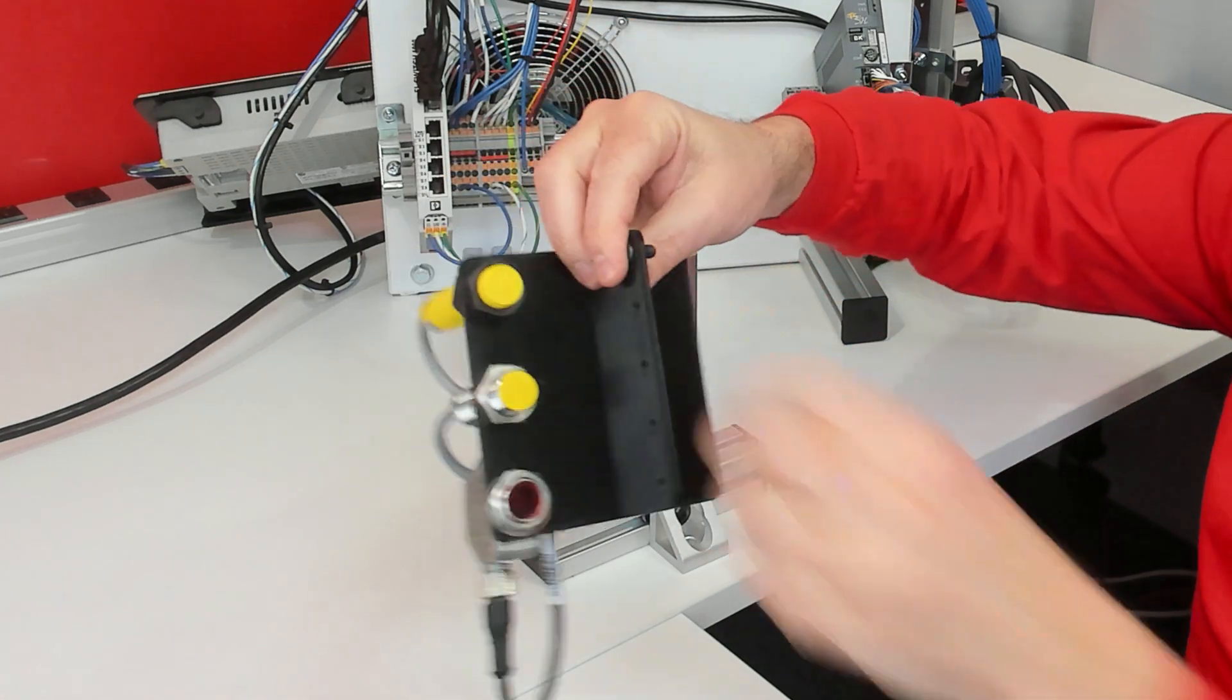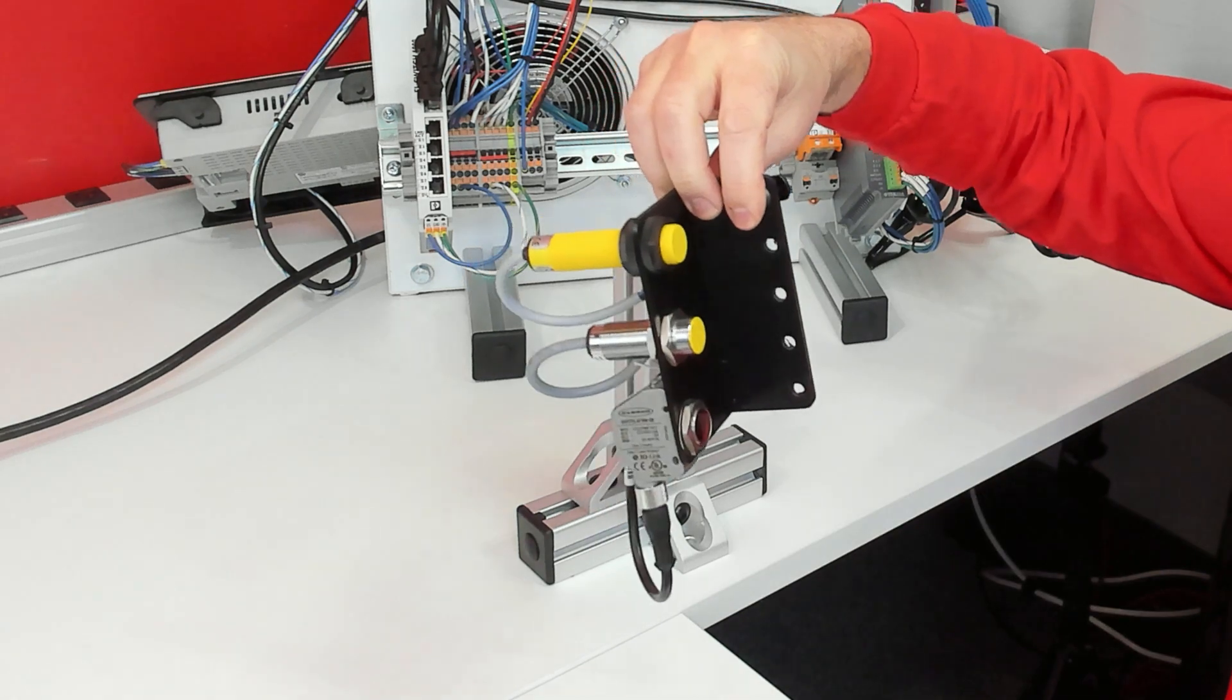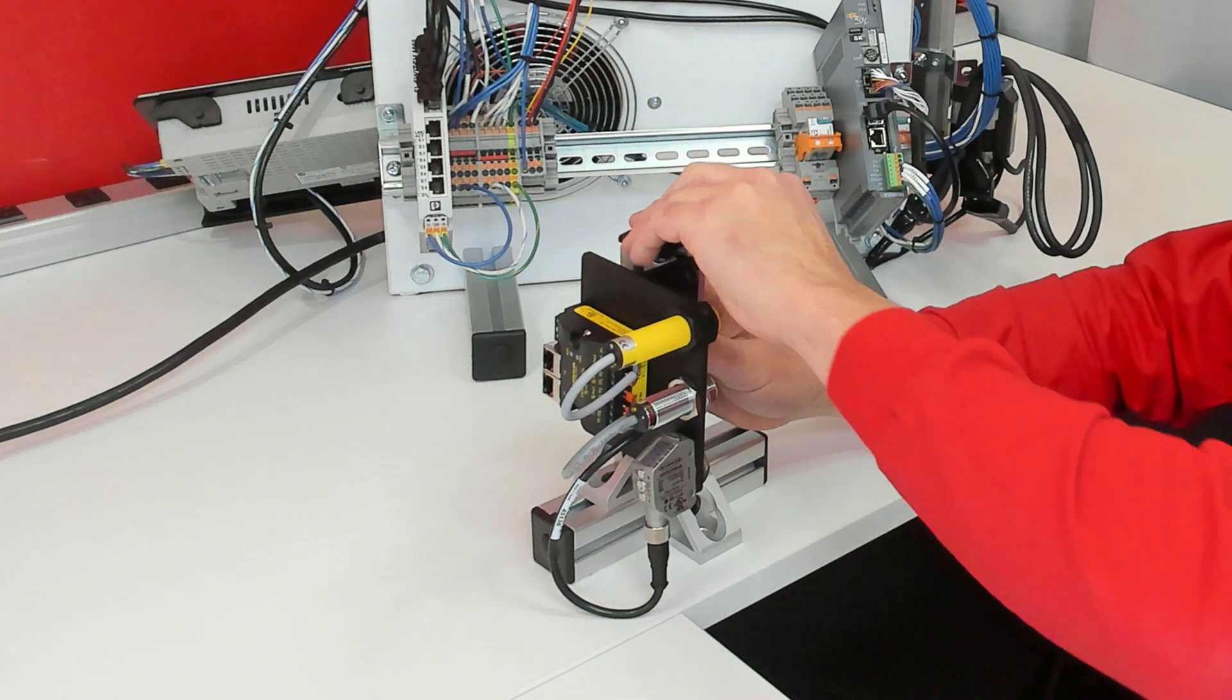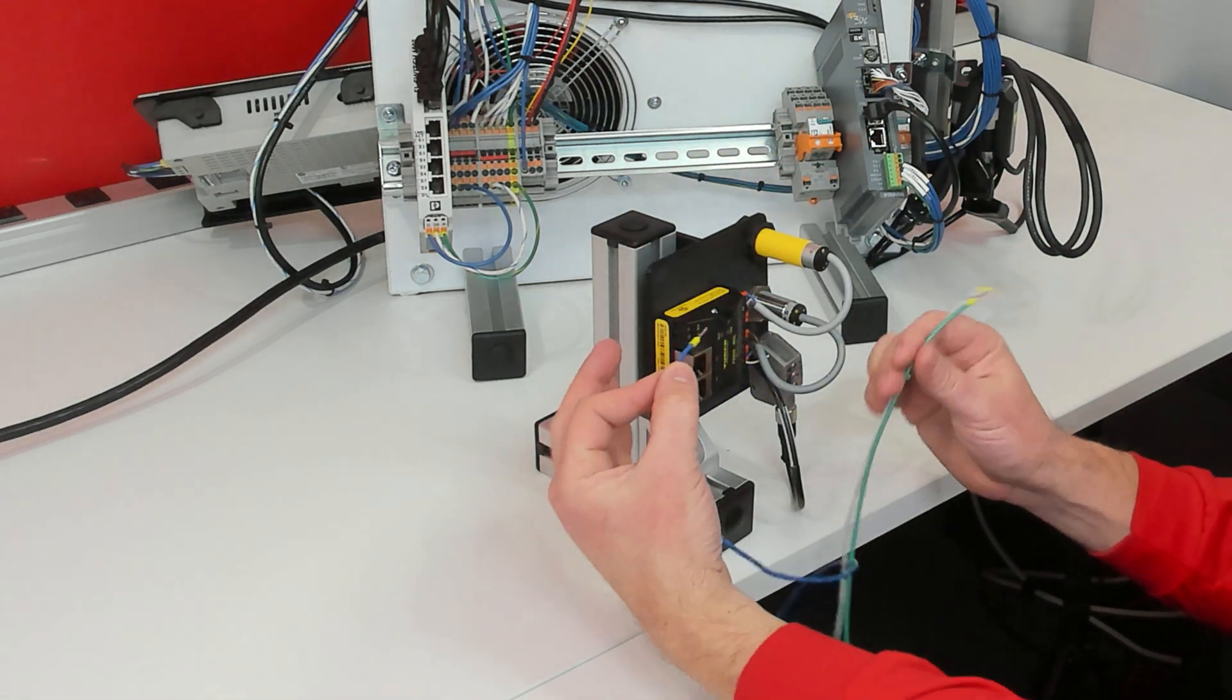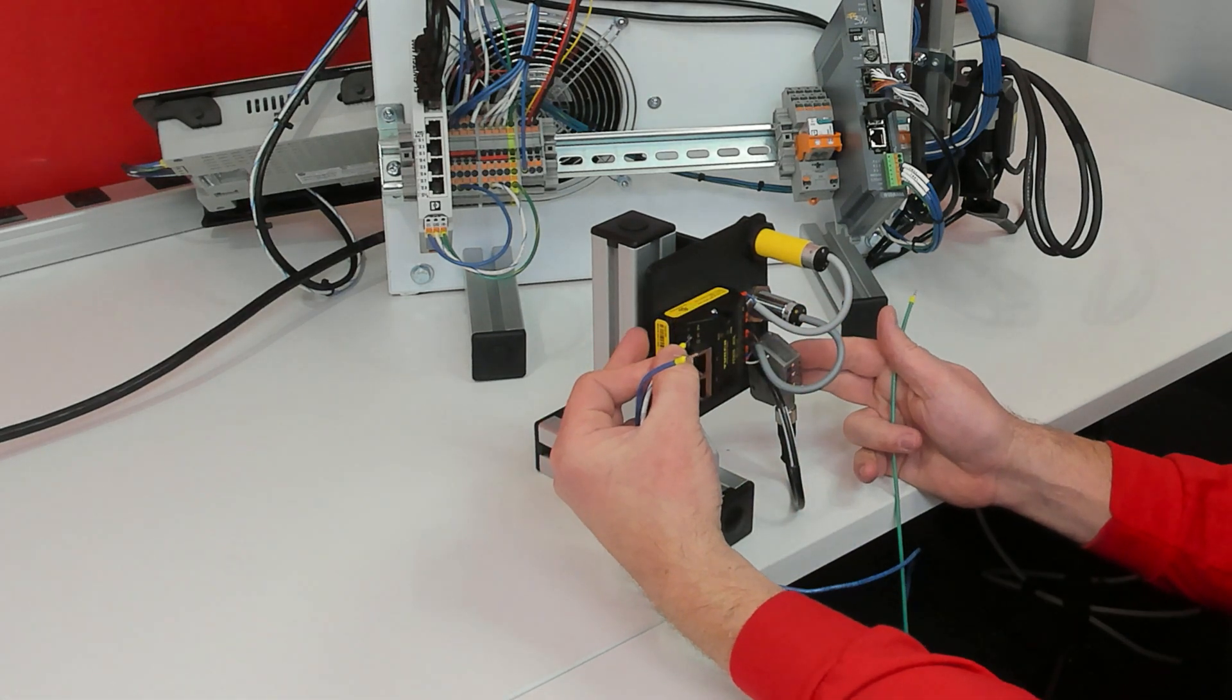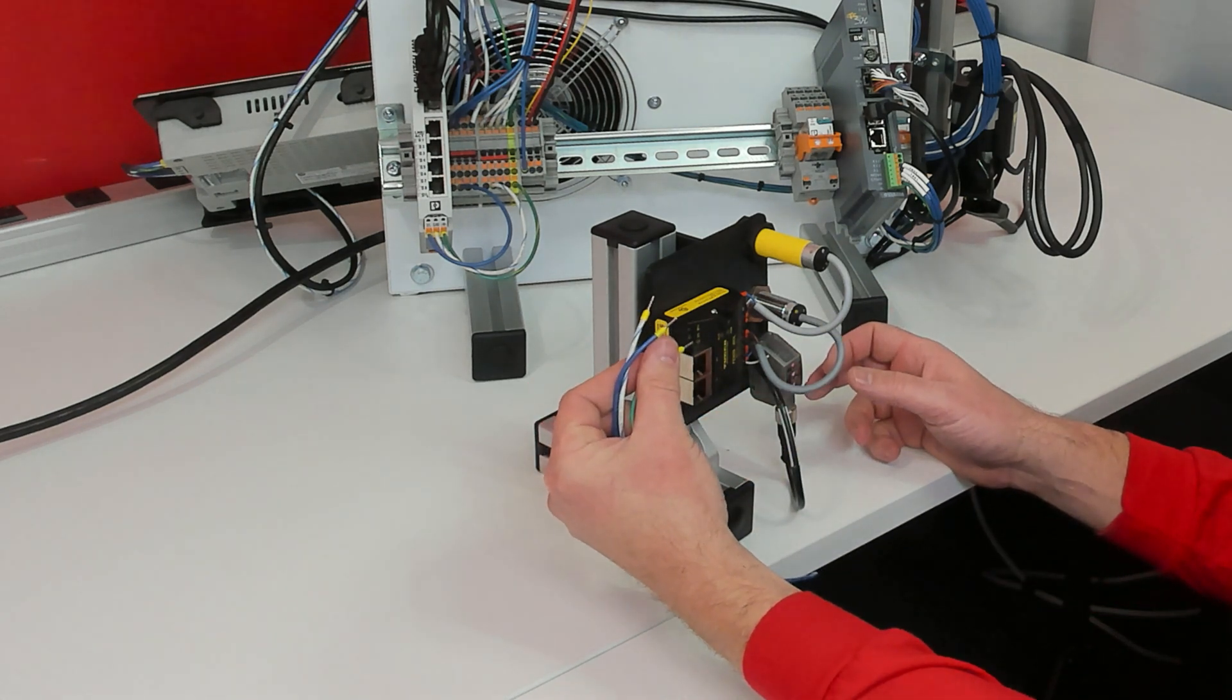We can simply put those into two of the mounting holes, then slide it down into the aluminum extrusion, and put your end cap on the top of it. Then it comes with three wires. Your blue wire is going to go to the V1+, your white with the blue stripe will go to the V1-, and the green will go to the ground symbol.